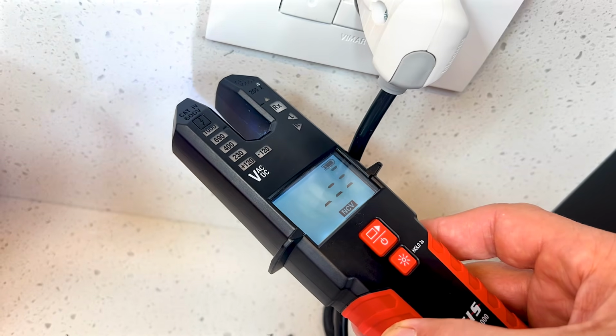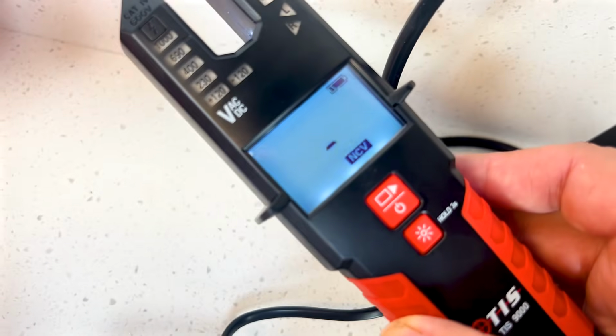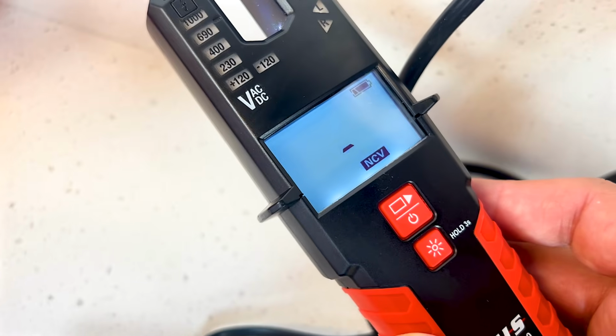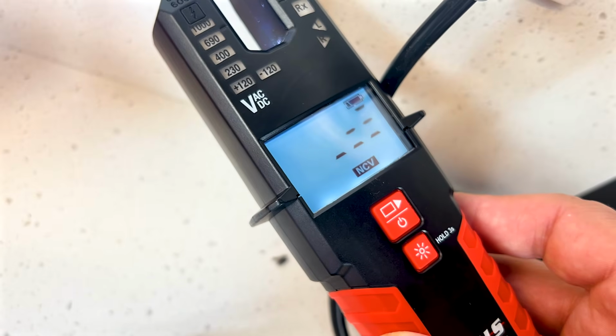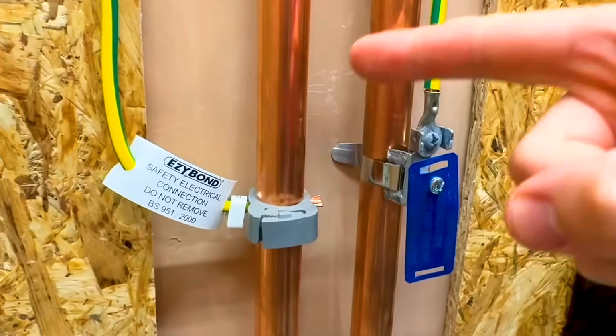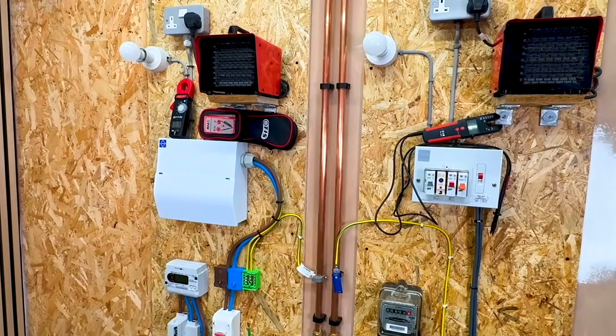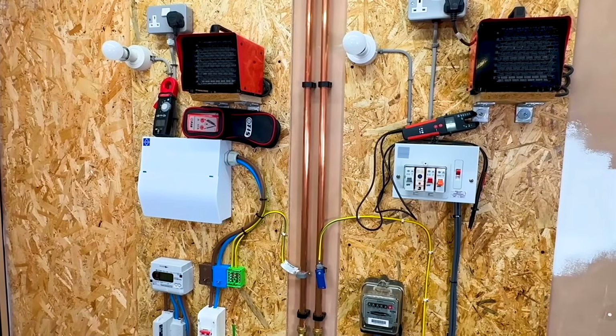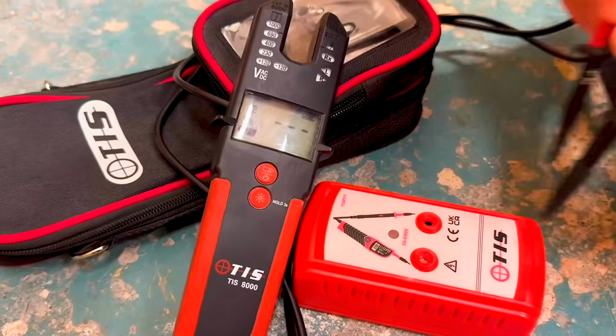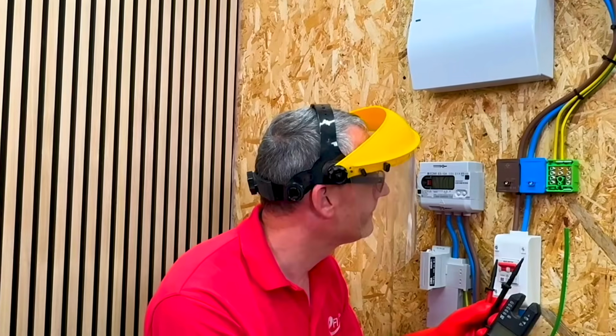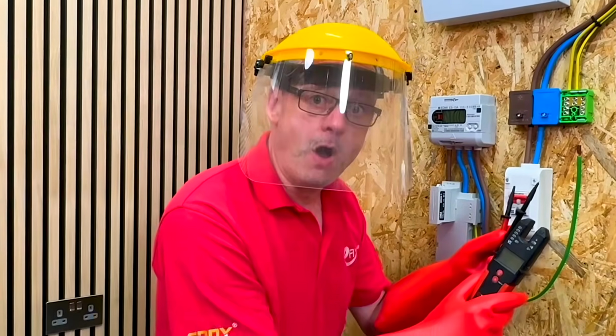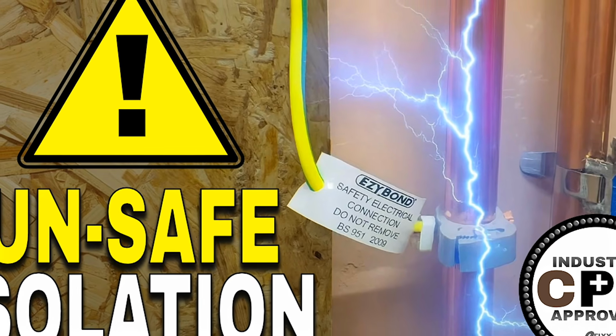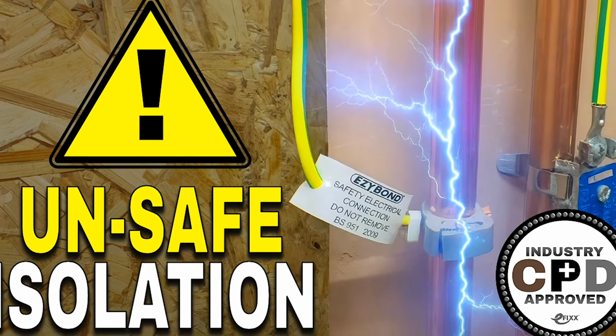On the side of the unit, there's also a non-contact voltage detector. That's useful for quickly checking if an appliance has power or for identifying potentially dangerous situations like diverted neutral currents in TNCS earthing systems. And if you want to understand more about those risks or just refresh your safe isolation knowledge, I'll leave links in the description to the modules on our training hub. They're well worth your time.